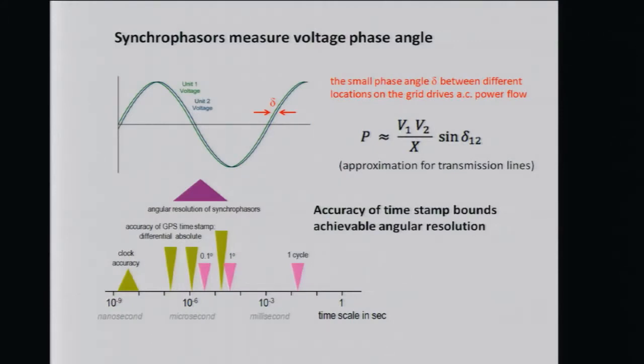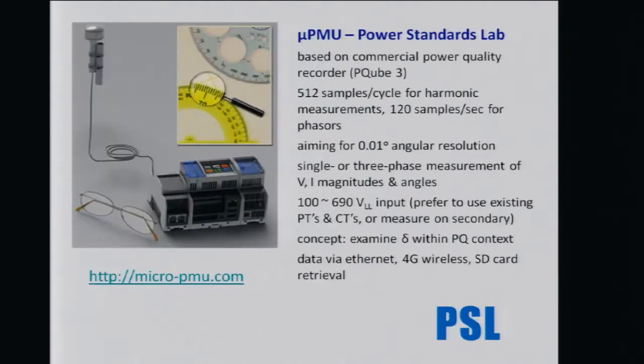The accuracy to which you can measure that phase shift depends on how good your clock is and your agreement at different locations about that clock. So what we're shooting for here, because the deltas are very small, down to less than a tenth of a degree, we're looking at the microsecond realm of synchronizing and comparing measurements. Measurements are time-stamped at different locations and then compared.